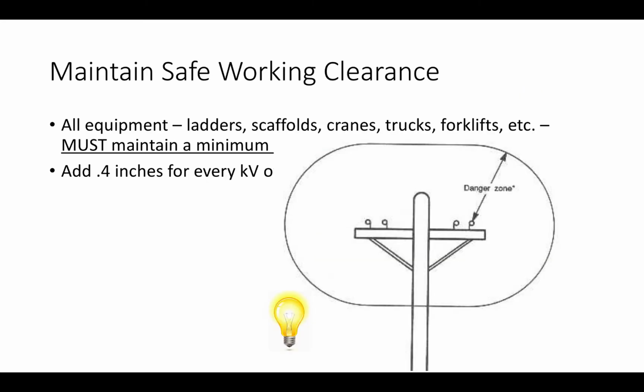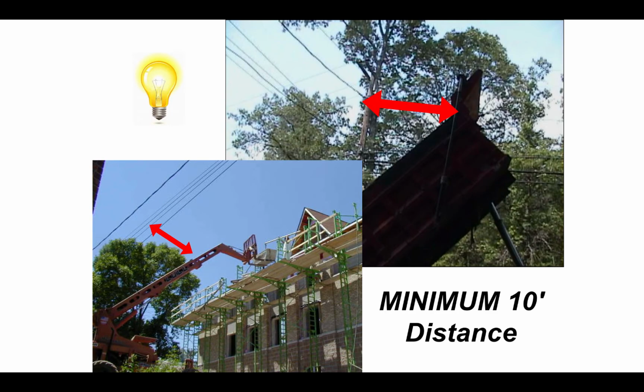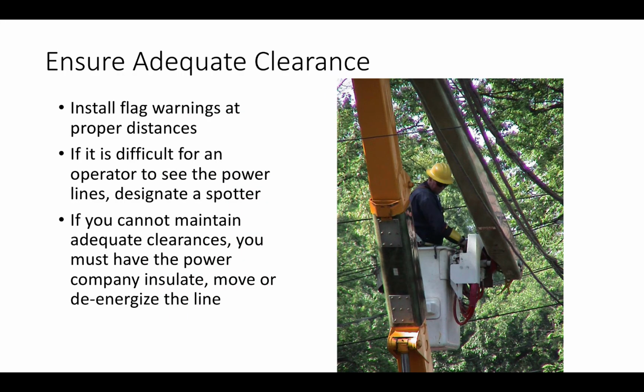You need to maintain safe working clearances from overhead lines. All equipment, that's ladders, scaffolds, cranes, trucks, forklifts, must maintain a minimum safety distance. You have to add 0.4 inches for every kilovolt. Minimum distance from overhead lines is 10 feet. Nothing can be closer than 10 feet. And if you have additional kilovolts over the standard, you have to add space.